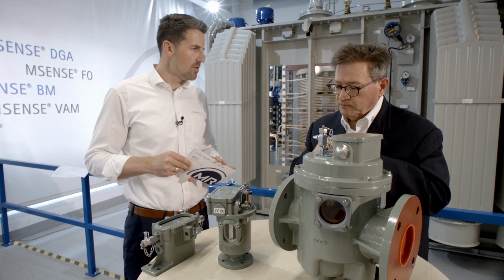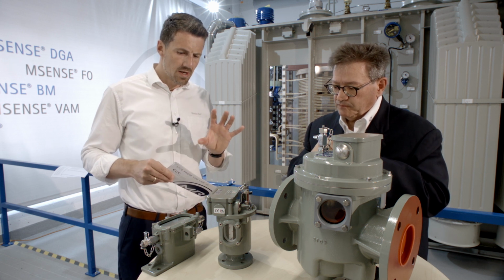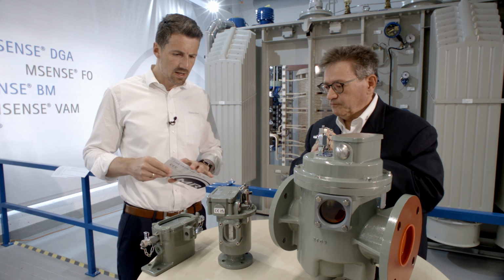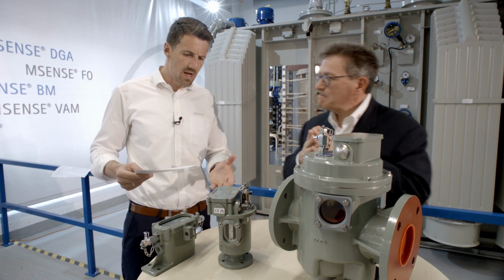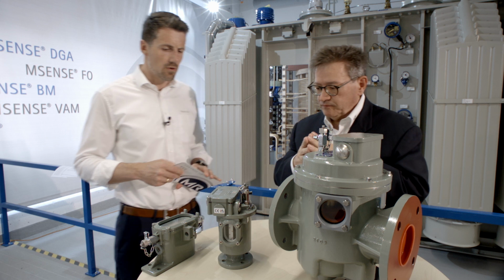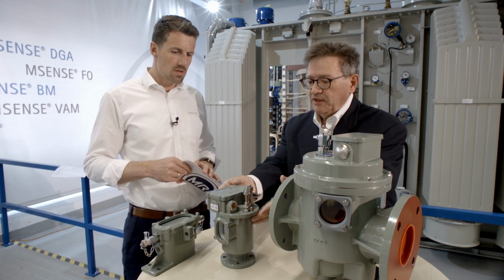Just quickly, at the end of our session here, talking about the gas relay and the gas collecting device, maybe you can explain to us the purpose, why these devices are used for transformers and for which kind of applications, of course. The CPR-free gas relay is a one-flange gas relay to be installed in the conservator of any kind of large, medium, small power transformers, if equipped with a rubber bladder. With a rubber bladder, okay.